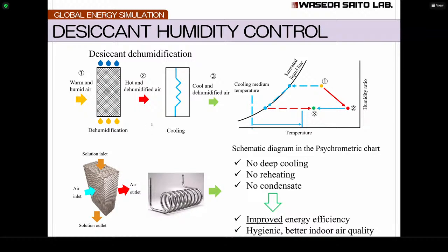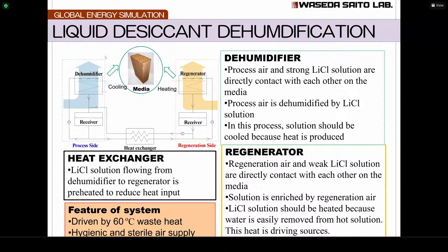So this is a configuration of liquid desiccant dehumidification systems. This system mainly consists of two parts, a dehumidifier and a regenerator. In the dehumidifier process, air and strong LiCl solution, this is a desiccant, directly contact each other on the media, this packed bed, as I've talked about. And process air, humid air, is dehumidified by the LiCl solution, the liquid desiccant. And in this process, as I've said, the solution should be cooled down because heat is released. And then when this liquid desiccant absorbs a lot of water, it cannot absorb water anymore.